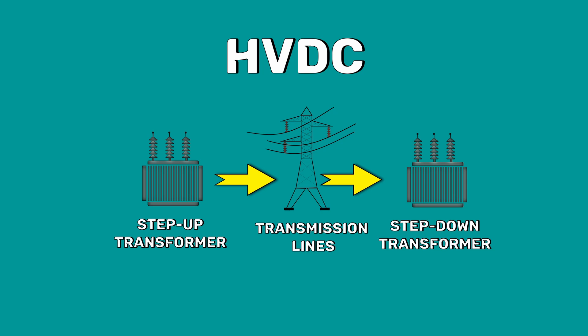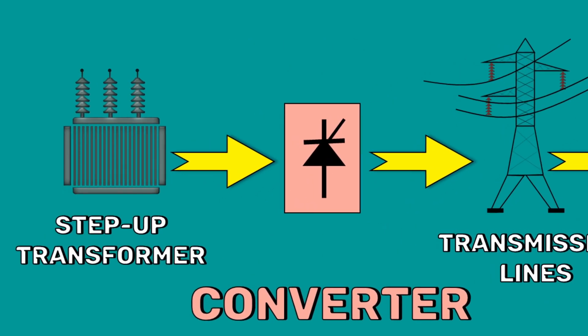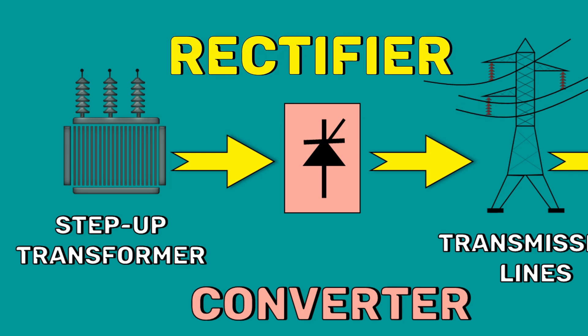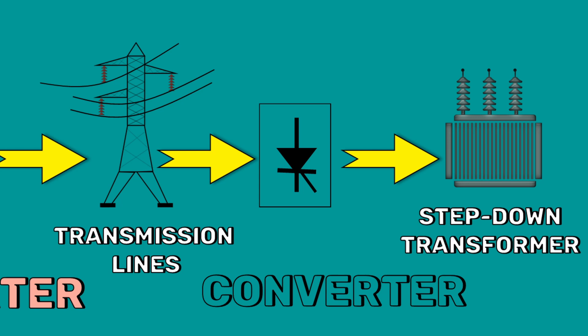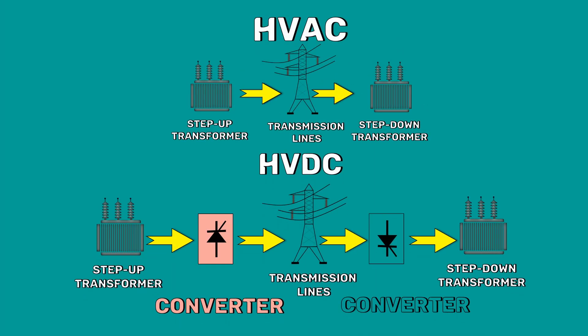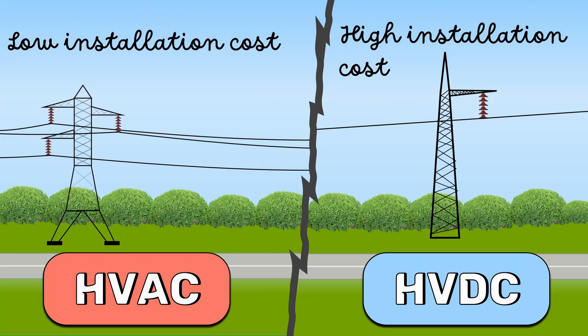High voltage DC transmission is very similar to high voltage AC transmission, except that it requires a converter at each end of the transmission line. The sending end converter receives the input from the step-up transformer and converts this high voltage AC electricity into high voltage DC electricity. This converter is called the rectifier. The receiving end converter receives the high voltage DC input and converts it back to high voltage AC. This converter is called the inverter. The presence of converters will increase the installation cost of the HVDC transmission system, as these semiconductor converters are very expensive.